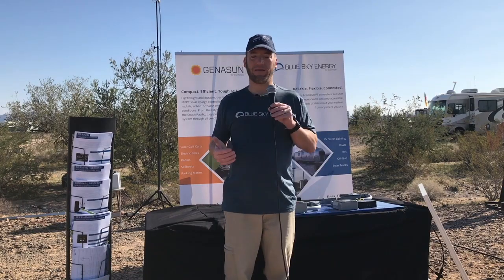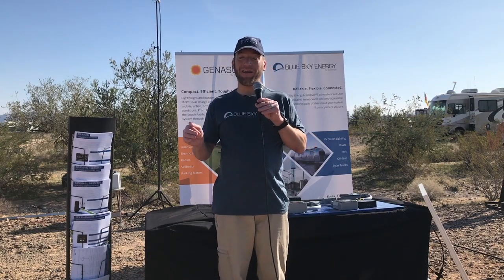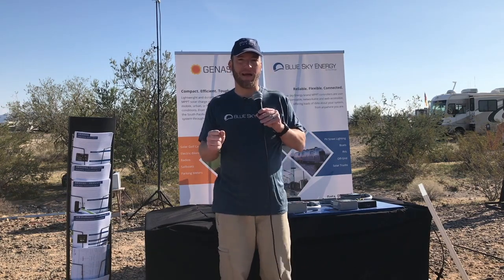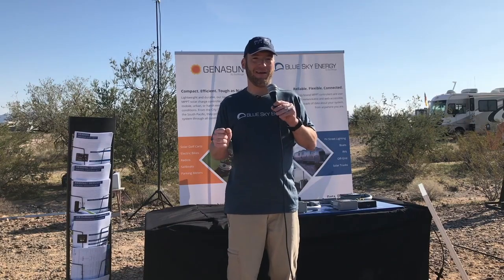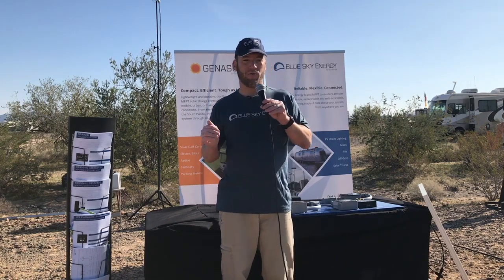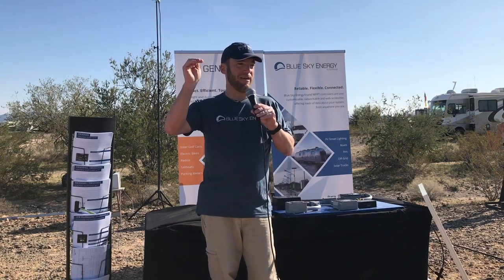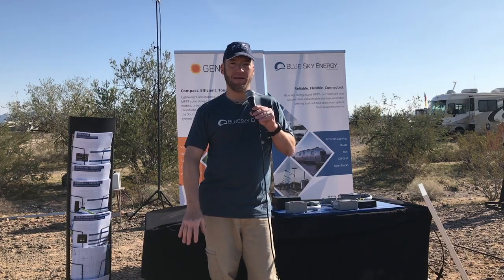Also, when you charge a lithium battery, once you achieve that balancing voltage, it's pretty much charged. You're in the 90 plus percentile, depending on how imbalanced your cells may be. Unlike a lead acid battery, where you're charging at 20 amps, 20 amps, 20 amps, and you get to absorption and it drops to 19, 17 amps, with a lithium battery you charge at 20 amps, 20 amps, 20 amps, and as soon as you get to 14.2, it drops to like half an amp, next to nothing.